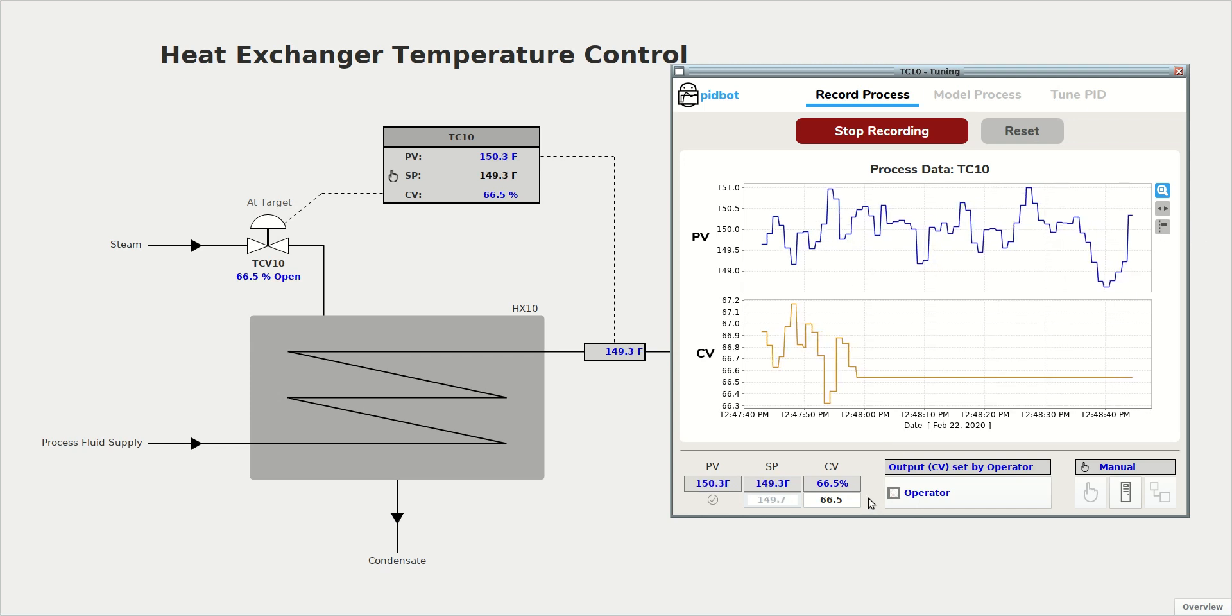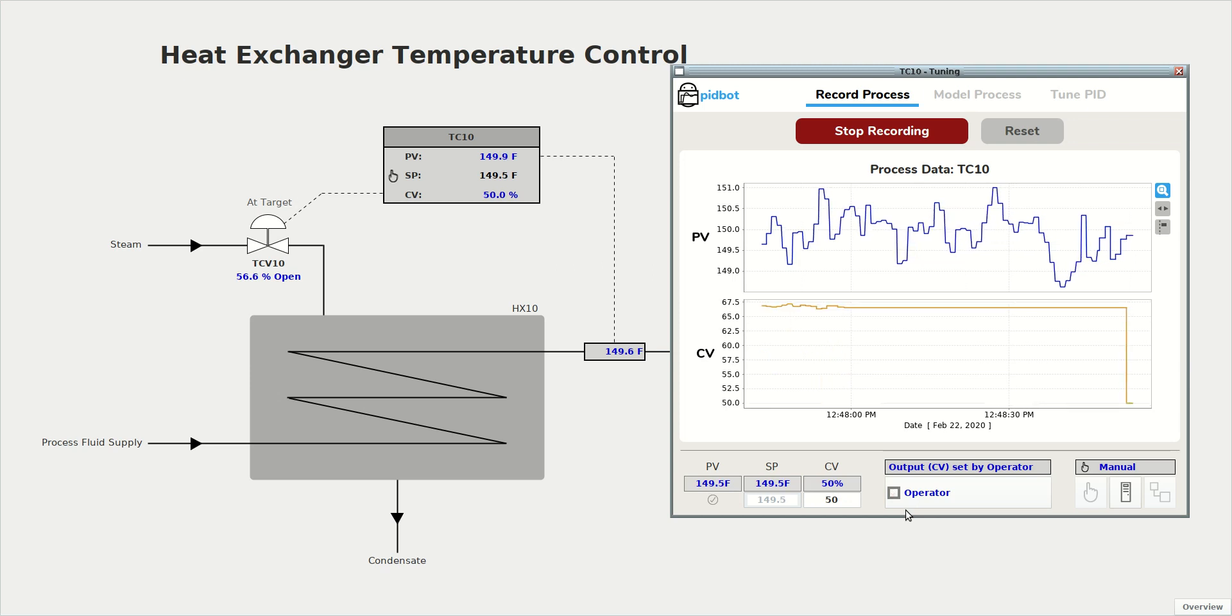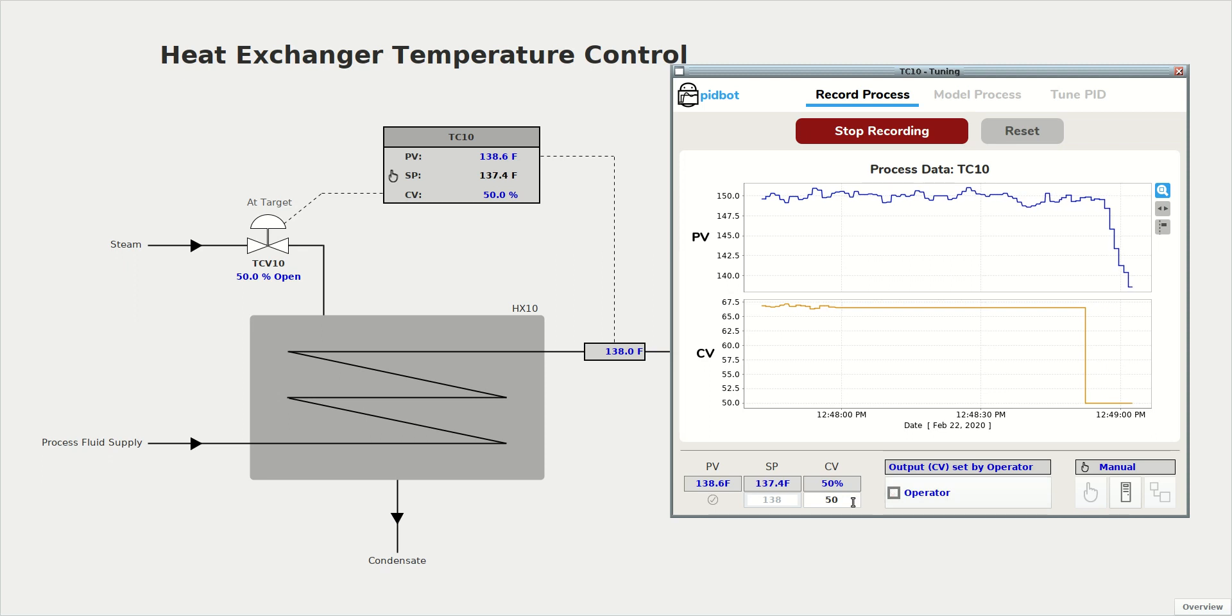So we can go ahead and bump the process. We're around 66% on the valve. Let's go down to 50. And you want to make sure you bump the process fairly sharply so that your response is far beyond any noise or disturbances in the temperature data. And in our case, we have a very clear response to our change in valve position.